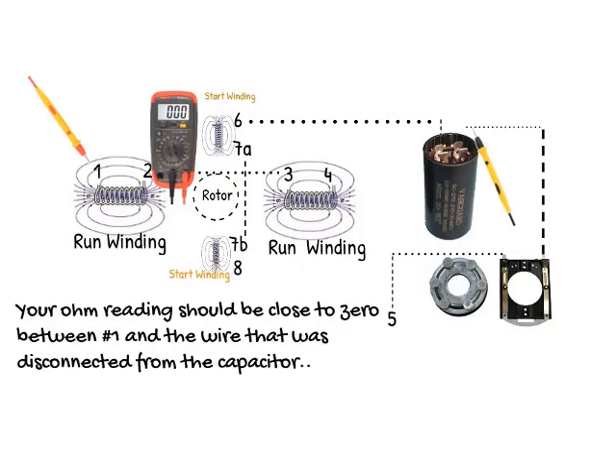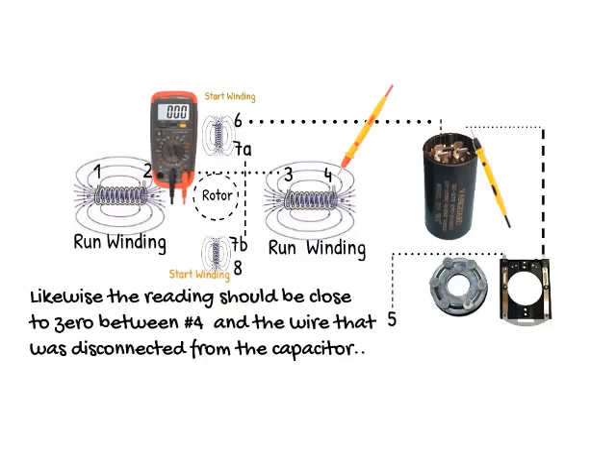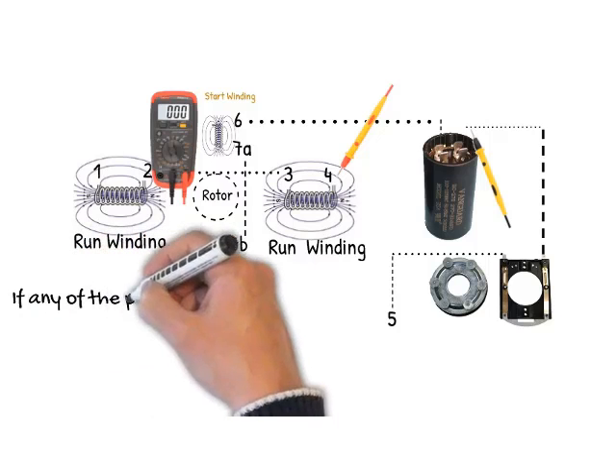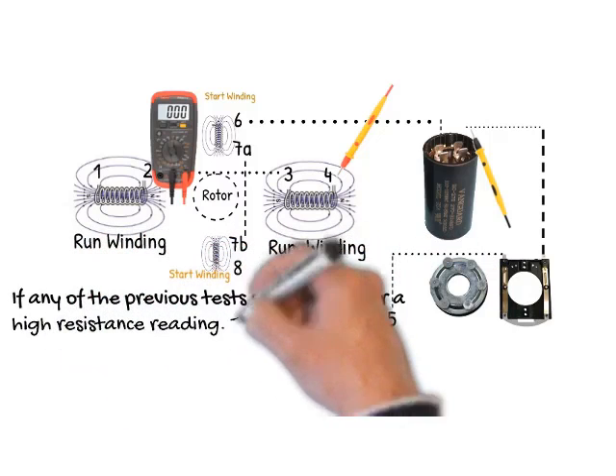The next test is similar to the previous, however, we will be connecting the test probe to the wire that we removed from the capacitor. Your ohm reading should be close to zero between number one and the wire that was disconnected from the capacitor. Likewise, the reading should be close to zero between number four and the wire that was disconnected from the capacitor.